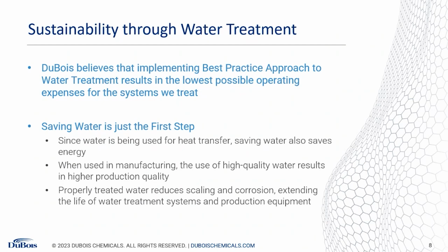So when you get to heat exchange surfaces, you can end up with scale on them if water isn't properly treated. That's a problem for a few reasons. Number one, the scale on the system adds weight, which eventually can cause the system to fail and need repair. Number two, the scale could plug up a system to where you've got to clean it out in order to get water flow. And number three, scale is an inhibitor in terms of heat transfer.